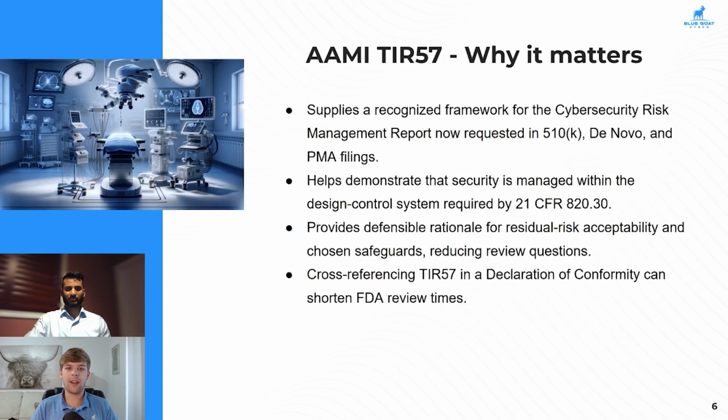All right, now we're getting into why it matters. This is a recognized framework for cybersecurity risk management, which is requested now in 510(k) submissions, de novo submissions, PMA filings, and more. Outside of even just the FDA, this can be helpful when trying to get entered into a healthcare delivery organization, something like Mayo Clinic, something like Johns Hopkins. They have their own cybersecurity requirements that can be fulfilled by a security risk management framework.